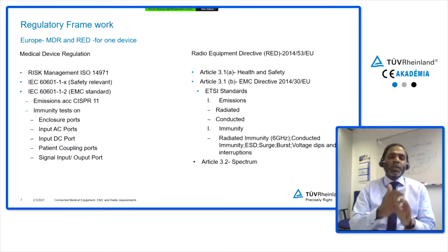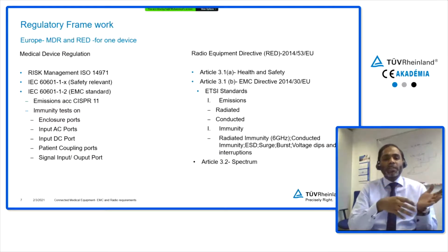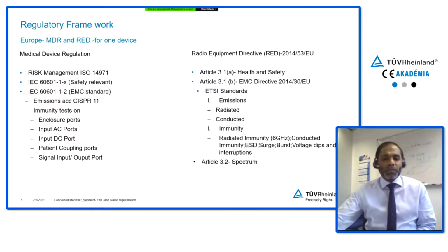So you might be asking, what's the difference between the EMC in IEC 60601-1-2 and the EMC in Article 3.1b? The EMC in Article 3.1b focuses on the wireless communication, whereas the EMC in IEC 60601-1-2 focuses on the essential criteria of the medical devices. That's a fundamental difference here.